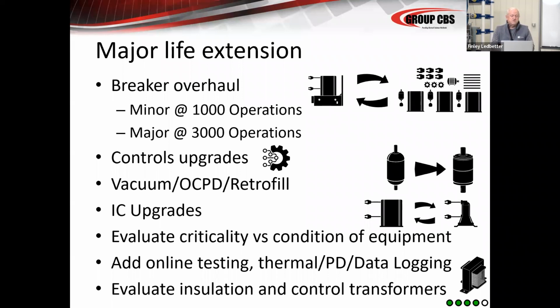At this point, you start to see some control upgrades, and I think that's what the last question was asking about. At this point, when the equipment's 50 to 75 years old, I think you'll see most of the controls upgraded: control wiring, cell switches, CTs, PTs, transducers, a lot of that stuff updated to whatever the new tech is. You'll see a lot of IC upgrades because the interrupting currents will have gone up, the systems will have stiffened, and you'll see a lot of people wanting to increase their arc flash capability or increase the interrupting capability of the breaker. And we're going to talk about that in segment 4.